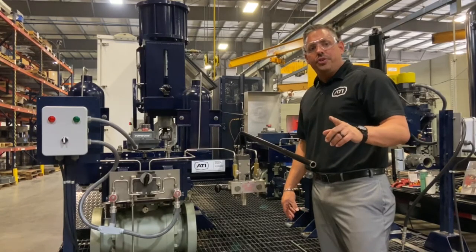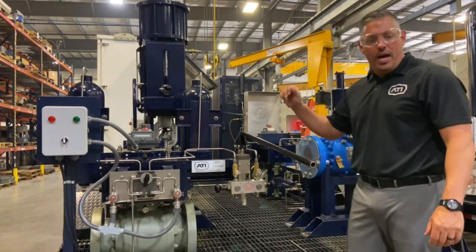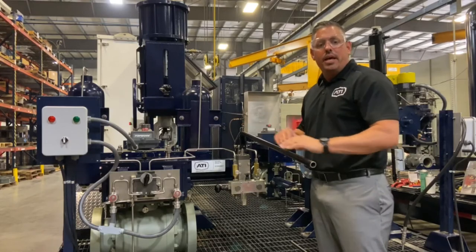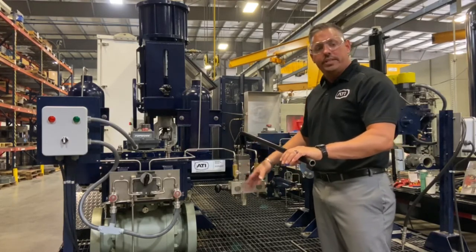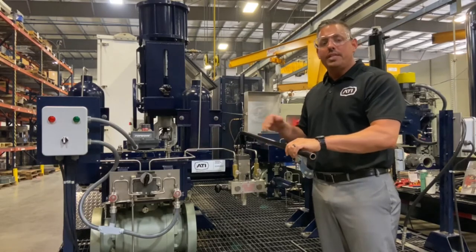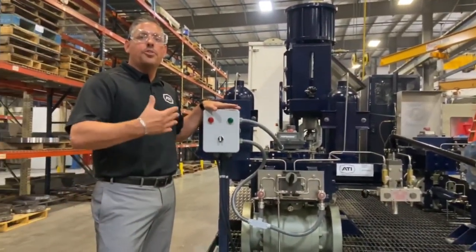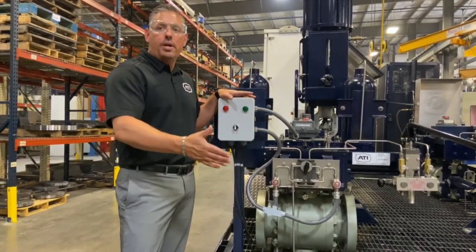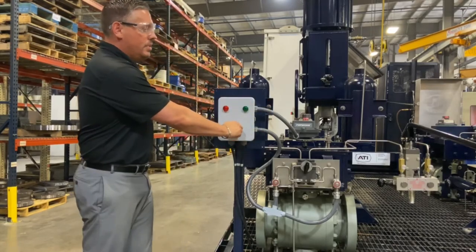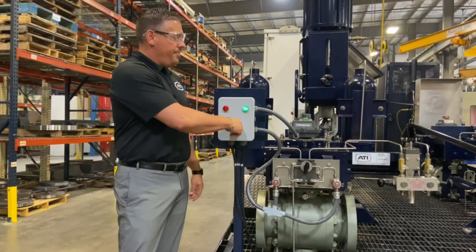Now we're going to demonstrate one of the safety features of our hand pump: it has an automatic reset. If the hand pump has been pushed in to open the valve and the control room sends a signal to close the valve, gas is going to be generated while somebody is on the hand pump. Without that automatic reset, it could move the handle very fast and actually hurt somebody. I'll demonstrate this as if from the control room — I'm going to send a signal to close the valve while the hand pump is energized, and you're going to see it go to automatic reset. Now it's going to exhaust out.